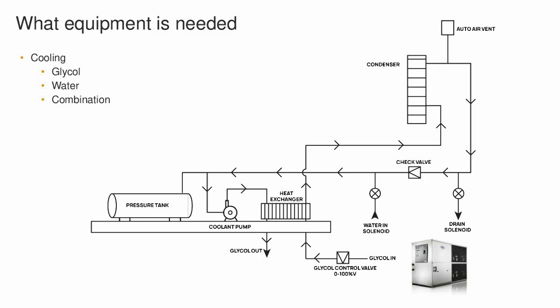This diagram that I have up there is a kind of unique way to separate a separate circuit for the still, but still using the same glycol loop that you have for all of your fermenters and bright tanks. So in essence, as you see that heat exchanger down below, we're just running your glycol through the loop, turning it on and off through that heat exchanger, and then we're running its own cooling loop for the condenser. And what's nice about breaking it out that way is that you could also have a water in and water out situation where you could actually use water just in case your glycol chiller goes down in the middle of a run. You could certainly jump into that water, and we even automate that too.